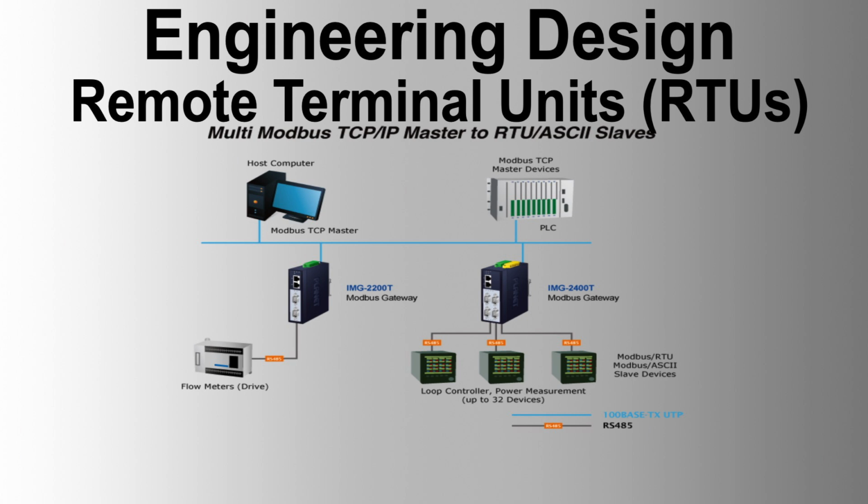Monitoring and simulation. Engineers can monitor and set the status of all inputs, outputs, timers, counters, and coils, as well as the contents of all registers in decimal and hexadecimal formats. The system also supports the disabling and forcing of all inputs, outputs, and coils to simulate system operations through the engineering workstation.